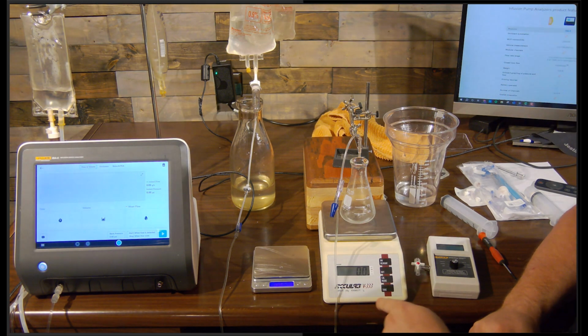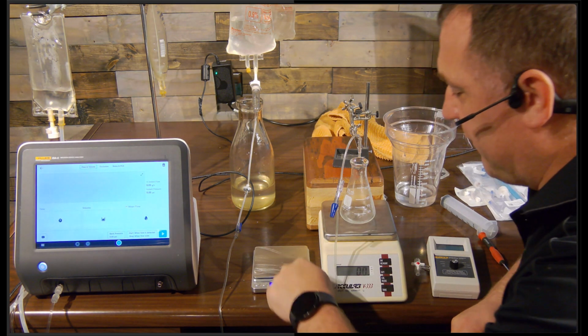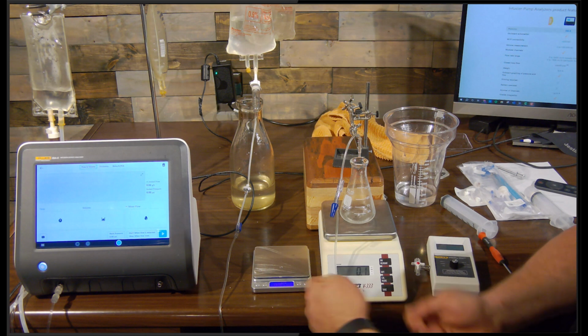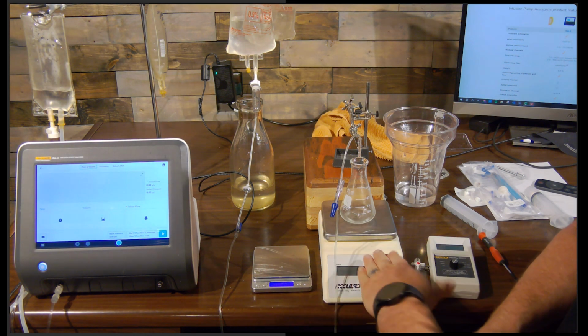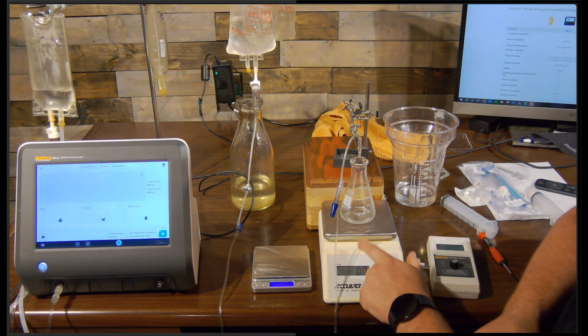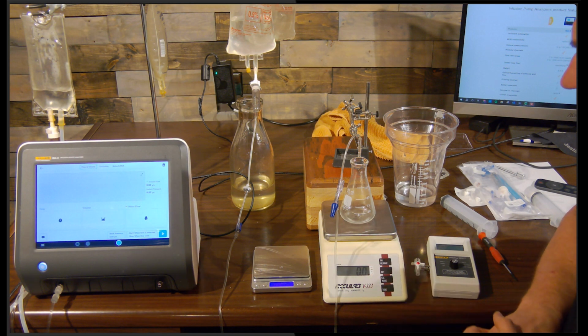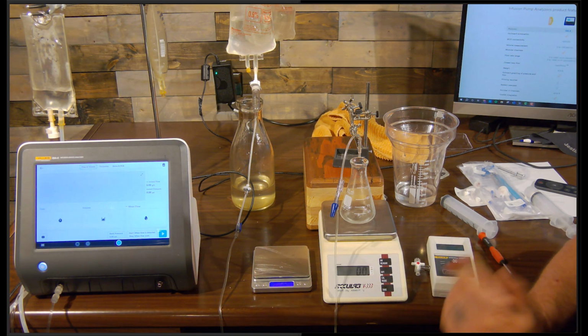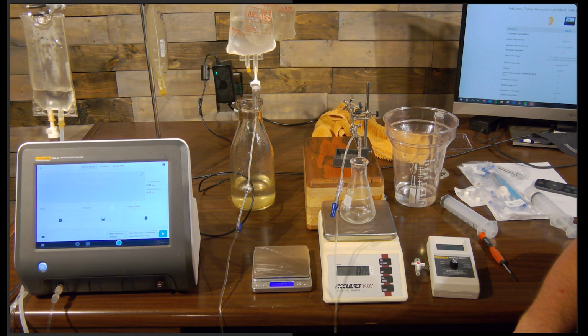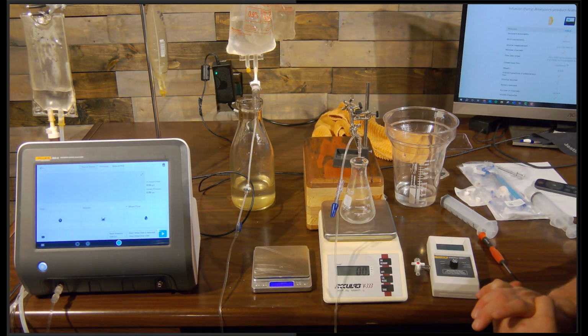Same with these scales. A lot of them will have a level bubble and some feet on them for the higher accuracy ones, and you have to make sure that scale is perfectly level, which means you really shouldn't be moving these things. So that's another little bit of a challenge that we'll talk about more here in the future. All right, so that's how we do our flow and our total volume tests with this method.